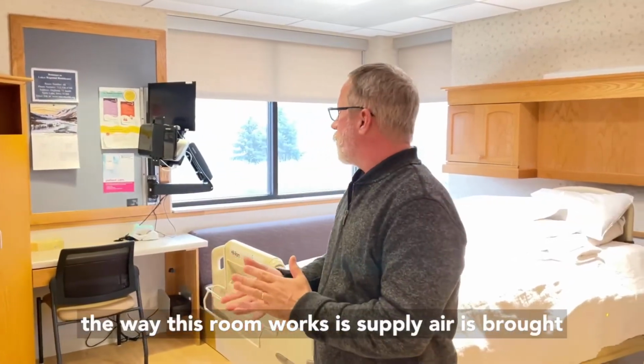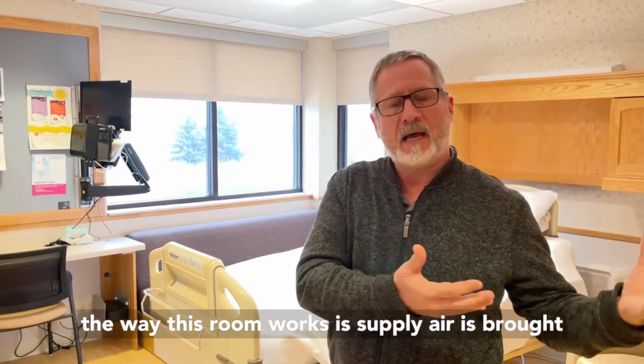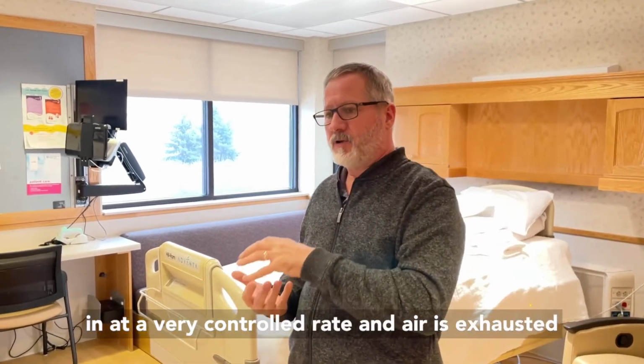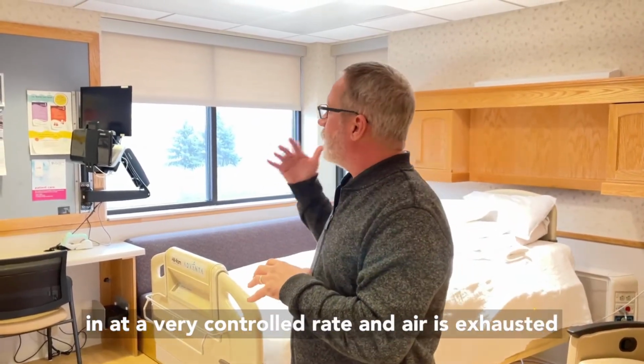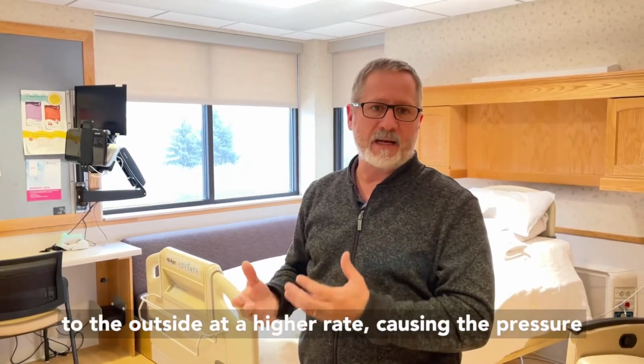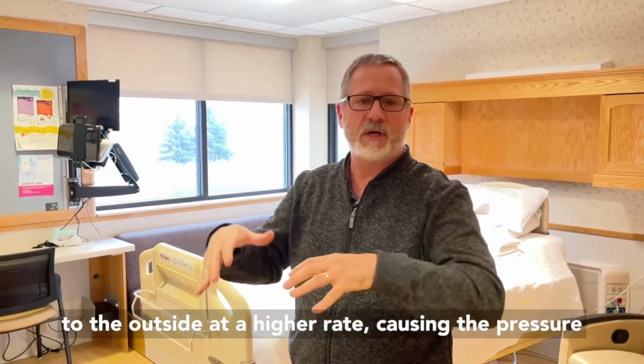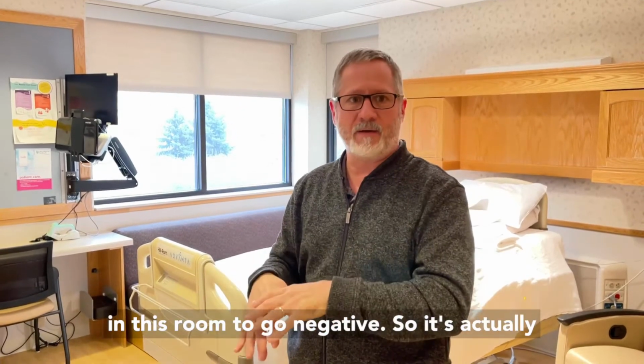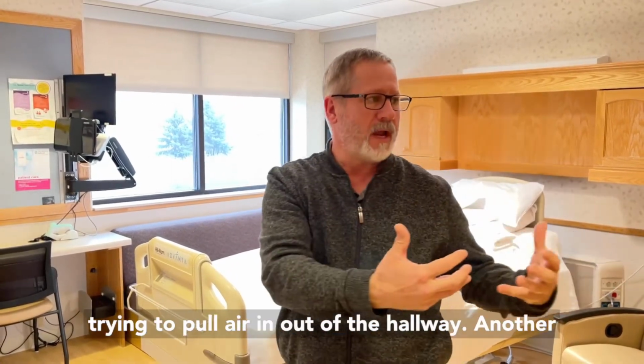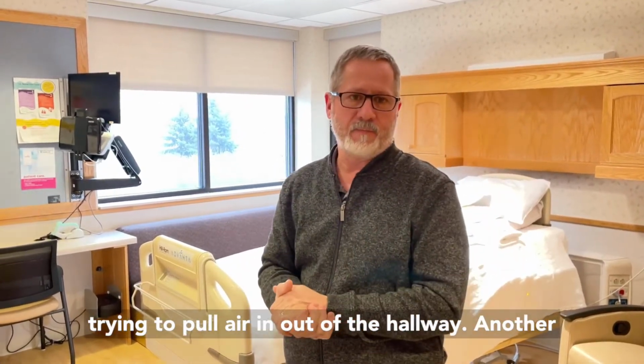So the way this room works is supply air is brought in at a very controlled rate, and air is exhausted to the outside at a higher rate, causing the pressure in this room to go negative. So it's actually trying to pull air in out of the hallway.